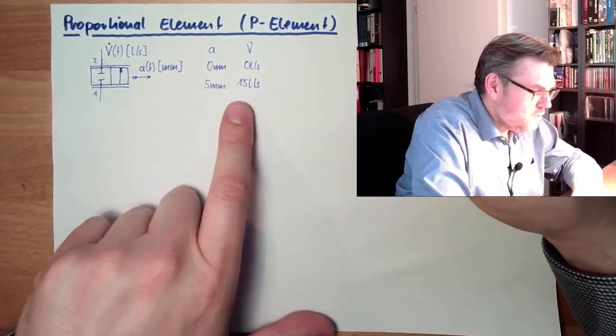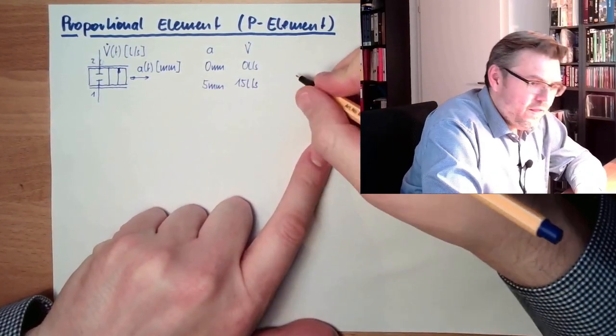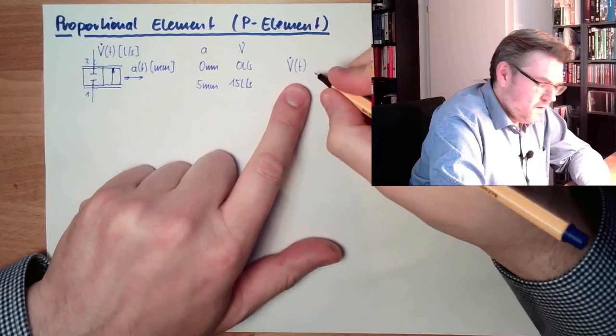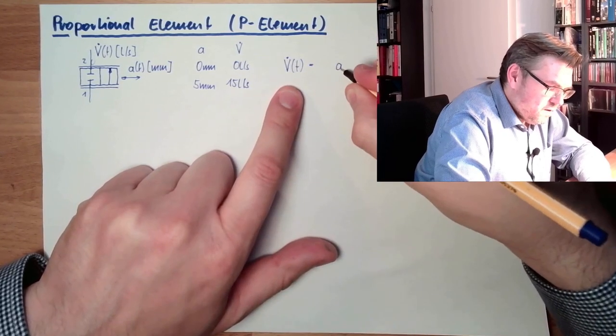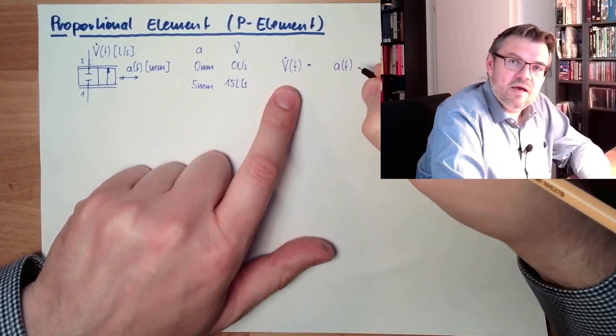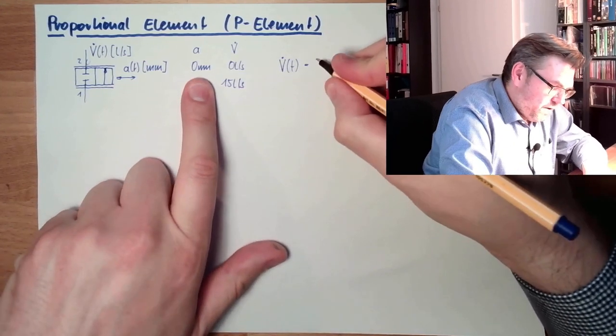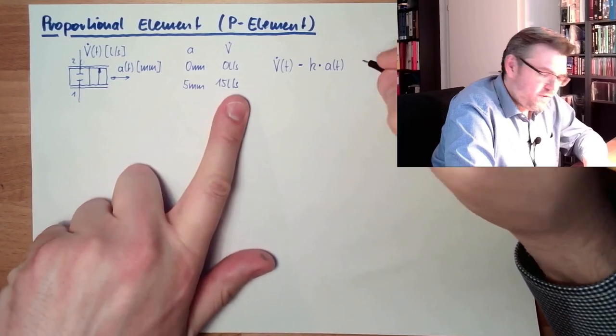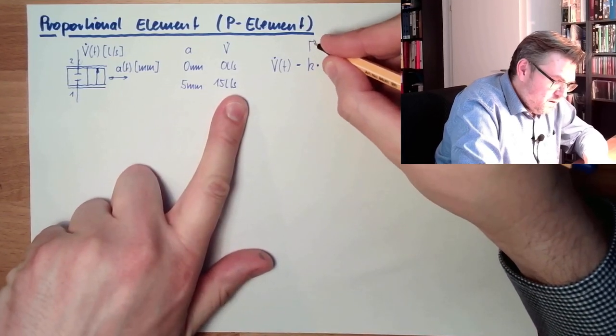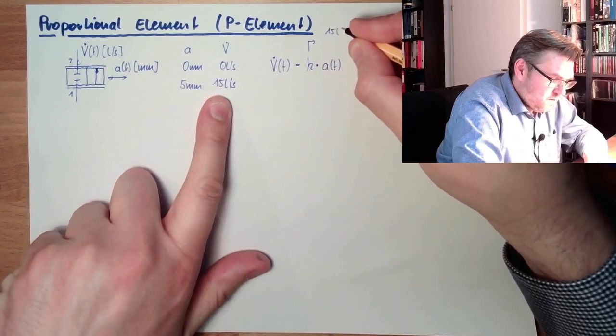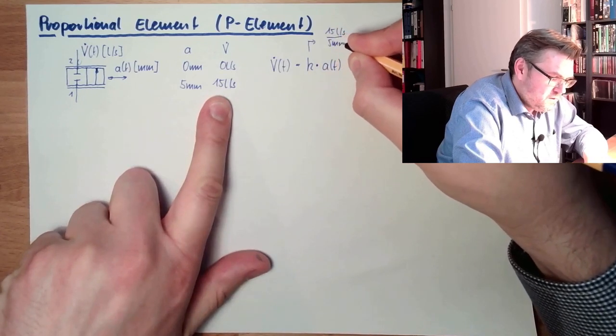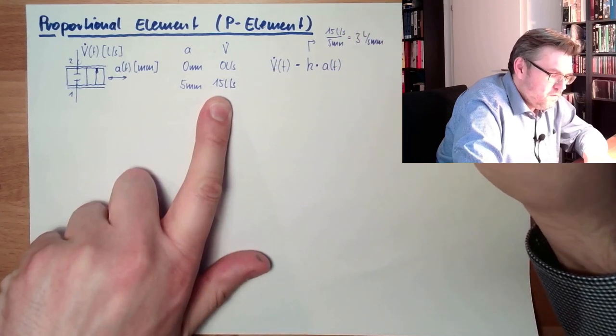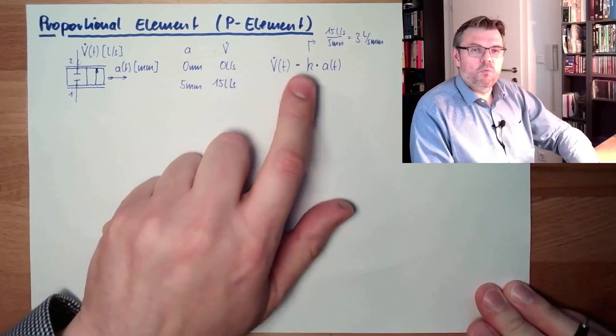We can adjust the flow through the valve by adjusting the valve opening. The current flow at a certain time equals the opening at that time multiplied by a proportional factor k. In our case, this proportional factor is 15 liters per second divided by five millimeters, which equals three liters per second per millimeter. This is the proportional factor k — three.